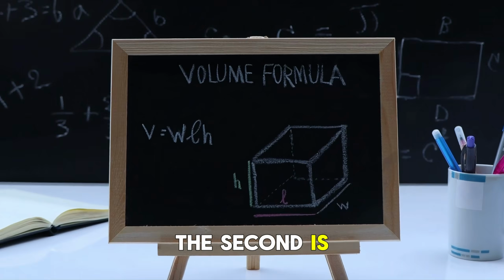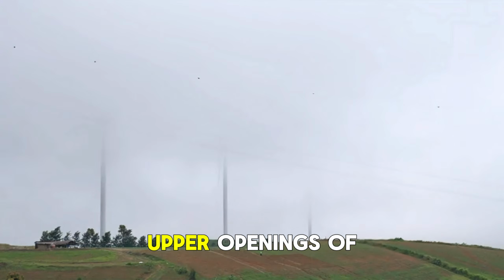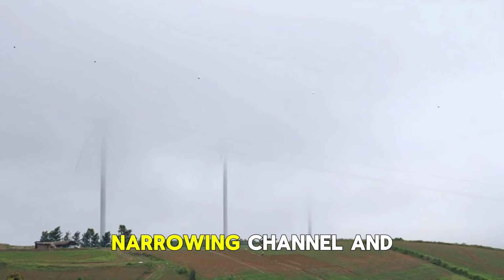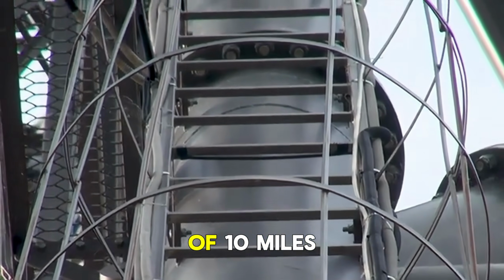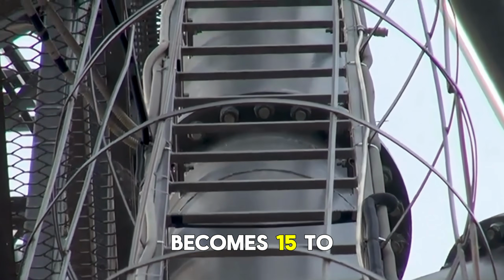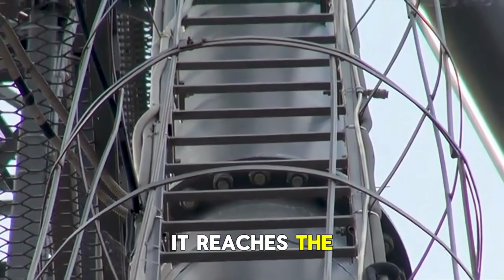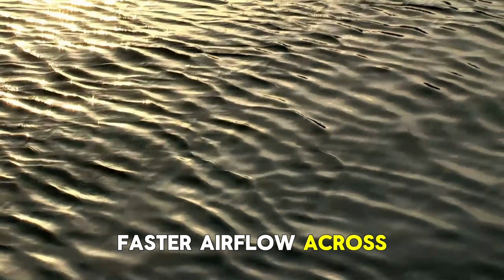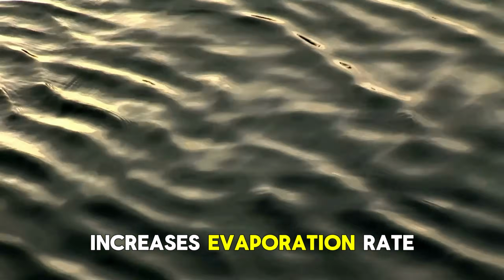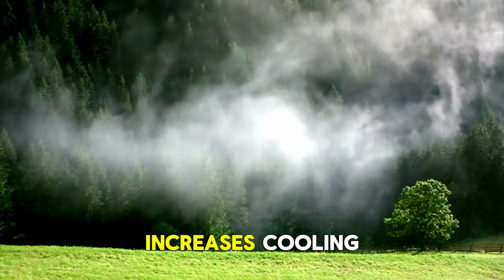The second is the Venturi effect. Wind striking the upper openings of the tower is forced into a narrowing channel and accelerates. A wind speed of 10 miles per hour at the tower opening becomes 15 to 20 miles per hour by the time it reaches the lower channel. Faster airflow across the water surface below increases evaporation rate, and increased evaporation rate increases cooling.